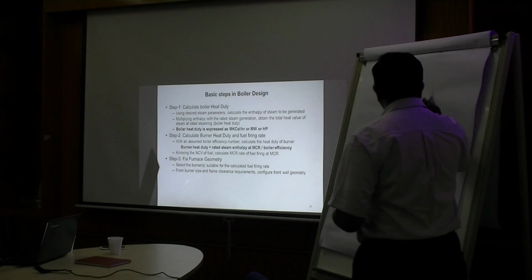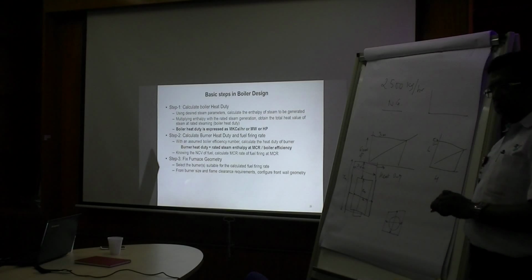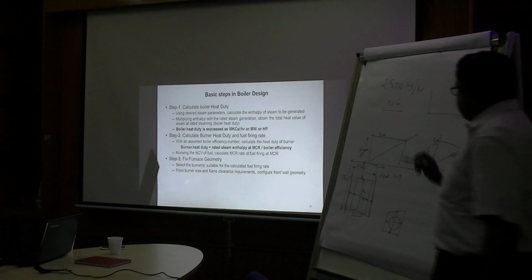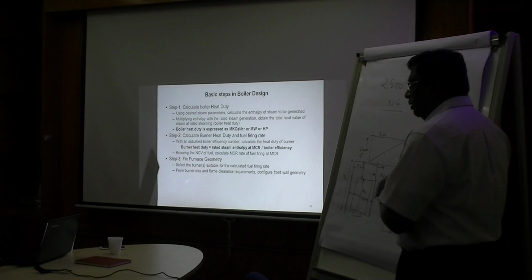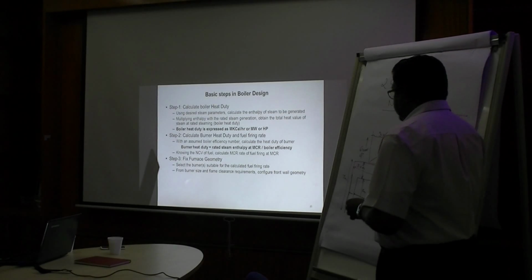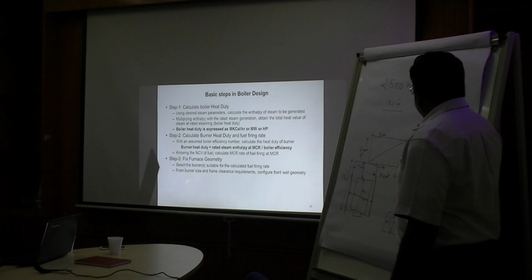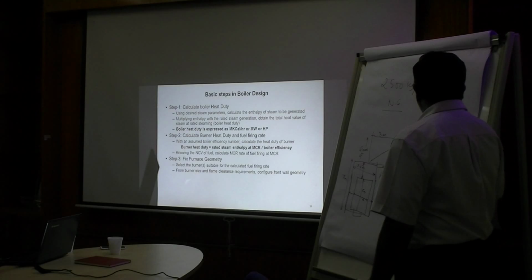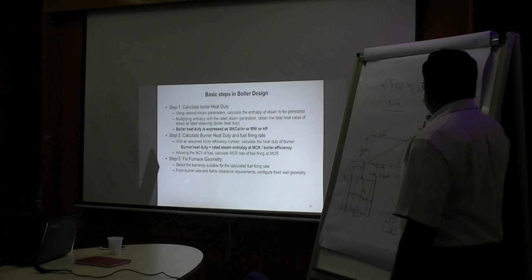It so happens that each model, let's say you take the biggest standard model of a burner, is normally supposed to be around 60 tons per hour. That means, if this is the number of burners and this is the heat duty, your heat duty goes on increasing, let's say from very small to 1 million kilocalories per hour.